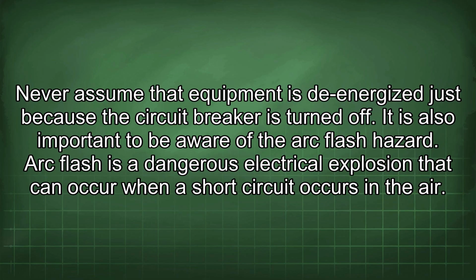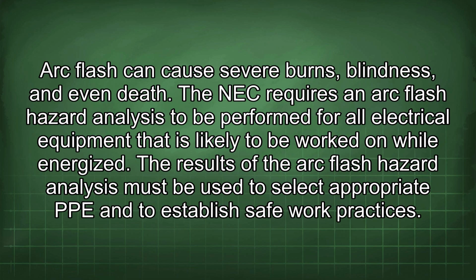It is also important to be aware of the arc flash hazard. Arc flash is a dangerous electrical explosion that can occur when a short circuit occurs in the air. Arc flash can cause severe burns, blindness, and even death. The NEC requires an arc flash hazard analysis to be performed for all electrical equipment that is likely to be worked on while energized. The results of the arc flash hazard analysis must be used to select appropriate PPE and to establish safe work practices.